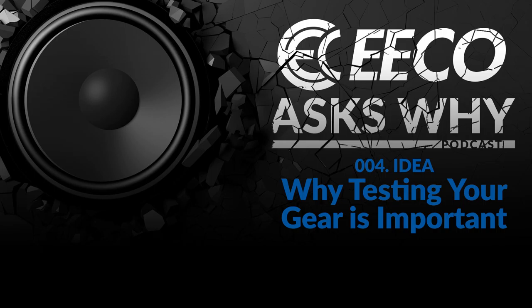Sure. Obviously, let's assume that the people going out are qualified. Let's make some general assumptions: that the breakers are all in good working condition and the electrical room is in good shape. We would first look at the breaker itself. What type of breaker is it? Does it have an electronic trip unit? Does it have a bimetallic or thermal magnetic trip unit? Many electronic trip units are equipped with what's called a cause of trip indication. That means if you walk up to a breaker that's tripped, you can look at the trip unit or plug a test set into the trip unit, and it'll tell you why it tripped.